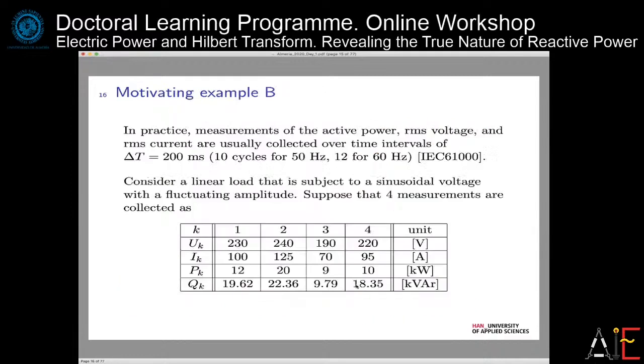Another example is this one, which is what I was referring to when defining the active power: that you have standards which tell you for how long you should do the measurement. Usually for the active power, RMS voltage or RMS currents, you take 10 cycles for 50 hertz signals and 12 for 60 hertz, so you have a measurement cycle of 200 milliseconds.